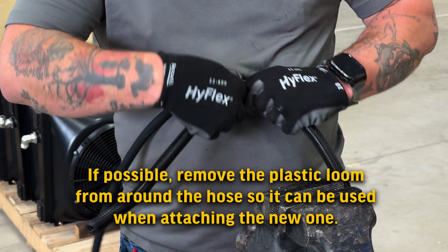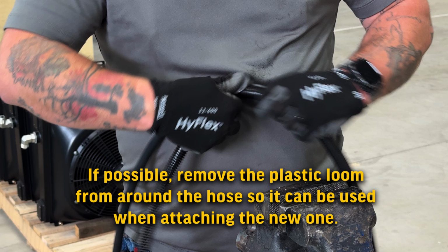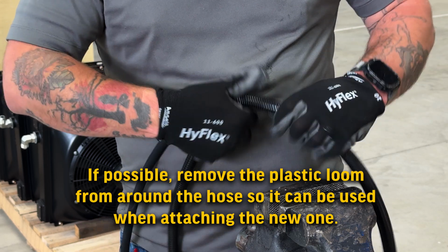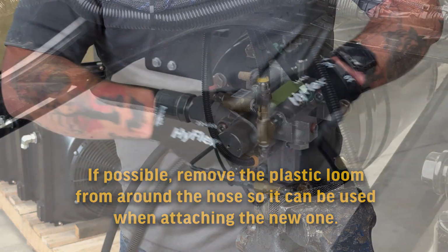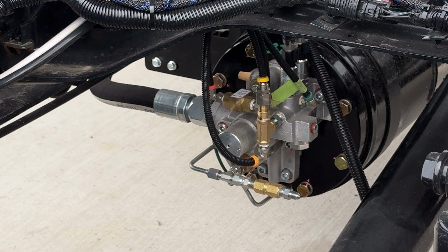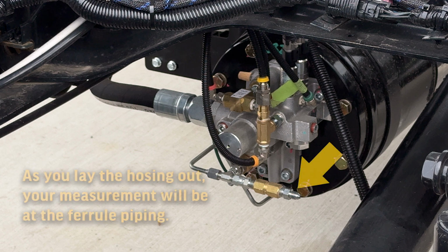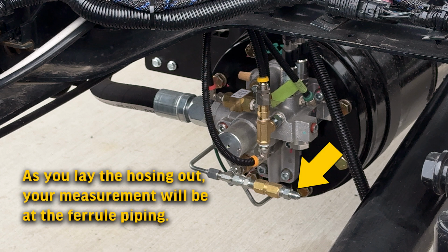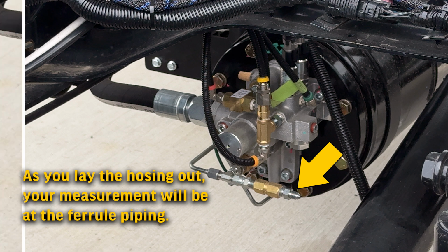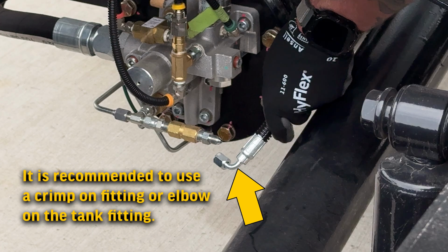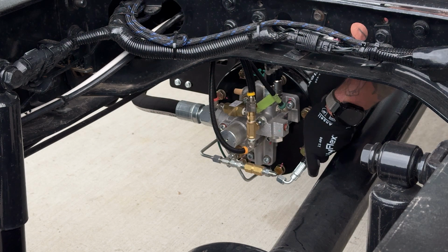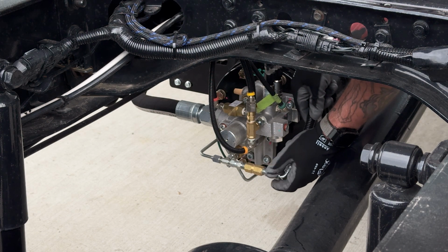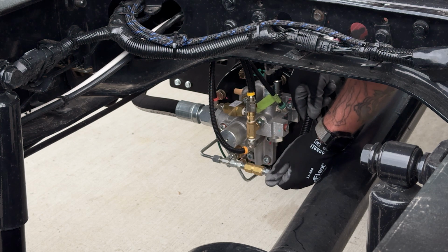If possible, remove the plastic loom from around the hose so it can be used when attaching the new one. Now let's measure for our replacement hose. As you lay the hosing out, your measurement will be at the ferrule piping. It is recommended to use a crimp on or elbow fitting at the tank location for the scavenge line. Attach this end of your hose to the scavenge line fitting located at the air oil separator tank.